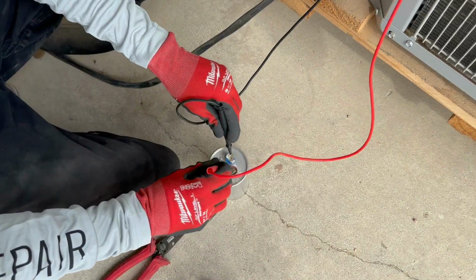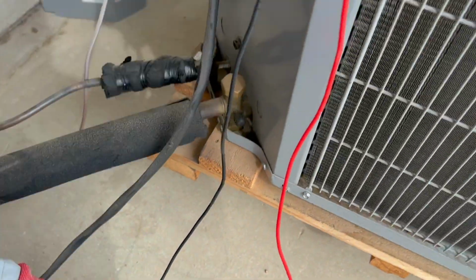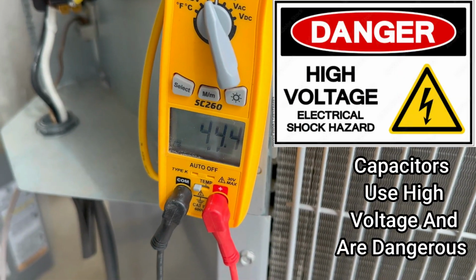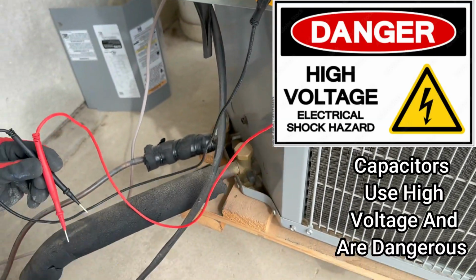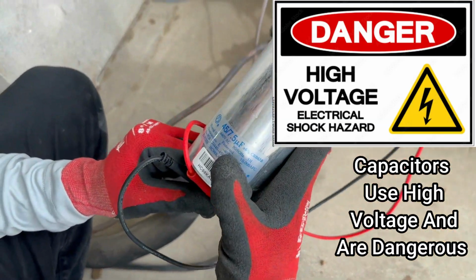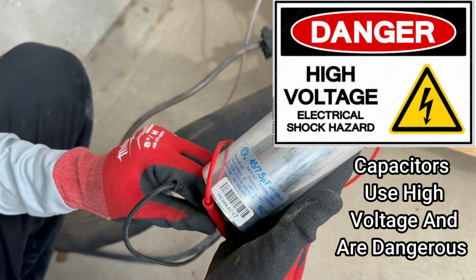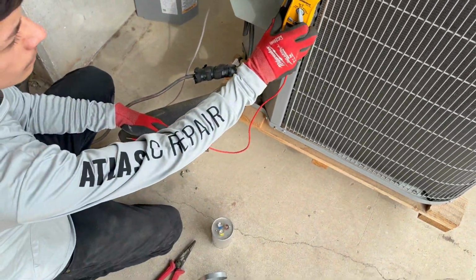So the run capacitor needs to be checked at least once a year, and I would recommend doing this before your AC gets heavily used, so basically in the springtime. Now obviously there are going to be more components that will wear out over time. However, the contactor and capacitor can wear out and can do a lot of damage downstream. So now let's jump over and talk about how you operate the system and the potential impacts that it might have.